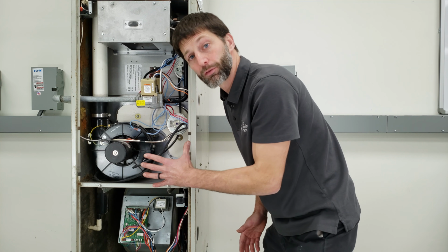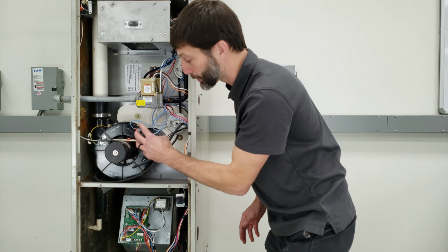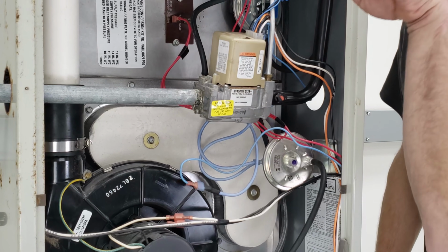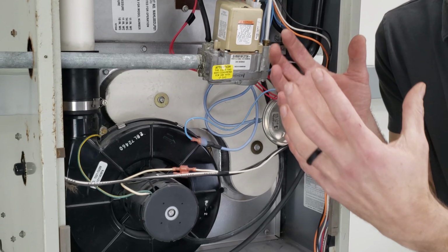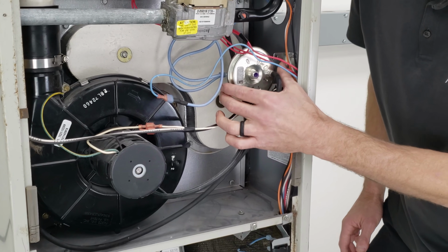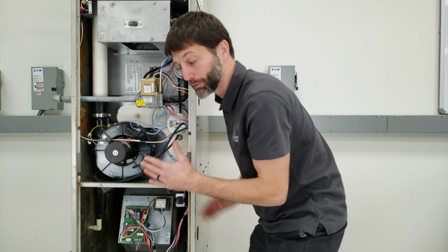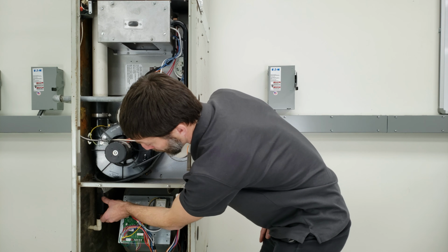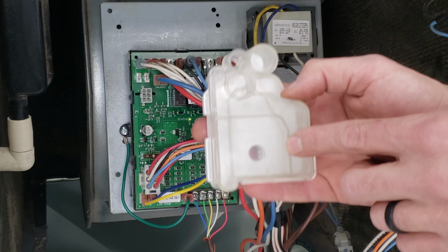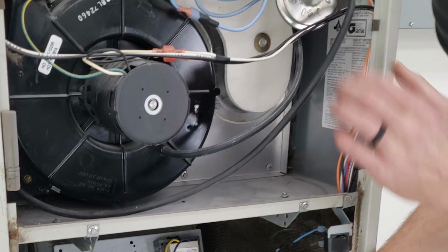Another thing on a gas furnace is that you could have a problem with water from the flame process. So you could have either water in your exhaust pipe, and if your pipe is not pitched properly, it could be full of water, and what's going to happen is it's going to mess up the pressure reading on the pressure switch. You could also have your condensate trap. Now this is one of the most common things that you could have as far as an intermittent problem, where the trap gets clogged sometimes, and then it drains slowly, and then all of a sudden you are able to have your pressure being read at your pressure switch, the proper pressure.